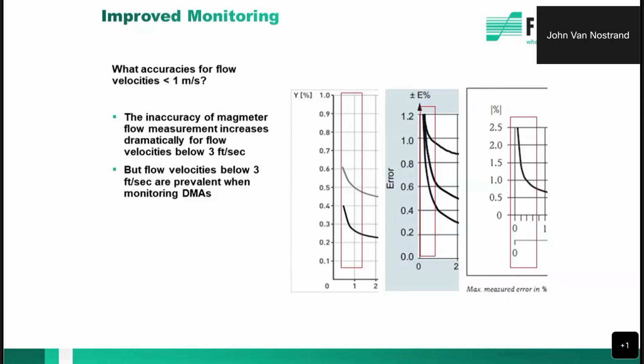So why below 3 feet per second? Like I said, that's the sweet spot for a mag. This is a particular calibration curve. So if you couple that with lead and copper, any injection of orthophosphates really exacerbates this. So this is from the flow rig, what the calibration curve looks like. And again, you see about 0.3 feet per second. You can see that you're getting up to about 2.5% versus the 0.5% that they advertise.